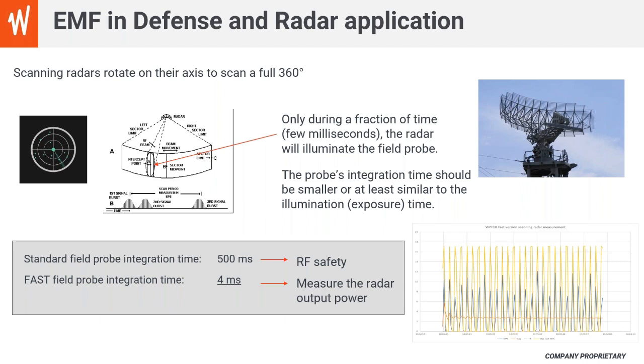But also, when you talk about these short signals that are seen in scanning radars, you have a fast integration time for the fast probes at 4 milliseconds, which allows you to measure the radar output. So it gives you the maximum RMS value, what we call the max fast RMS. This max fast RMS is the maximum of all the 4 millisecond samples taken in the sampling period, which the device gives you as a refresh on the screen, where you have the maximum level indicated. So in this case, it allows you to capture these short signals which are measured from these scanning radars.